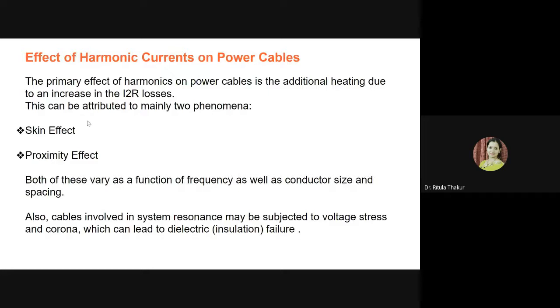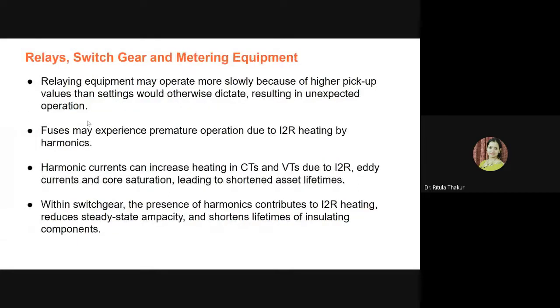Both the skin effect and the proximity effect are a function of the frequency as well as the conductor size and spacing. Also, cables which are involved in system resonance may be subjected to voltage stress and corona. This is not the corona you are thinking of; this is a different corona effect. This can lead to dielectric failure in the cables. Then of course these harmonics also affect our switchgear and protection devices like relays and metering equipment. Relaying equipment may operate more slowly because of higher pickup values than the settings would otherwise dictate, resulting in unexpected operation. So harmonics may cause deviations in the settings of the relay.